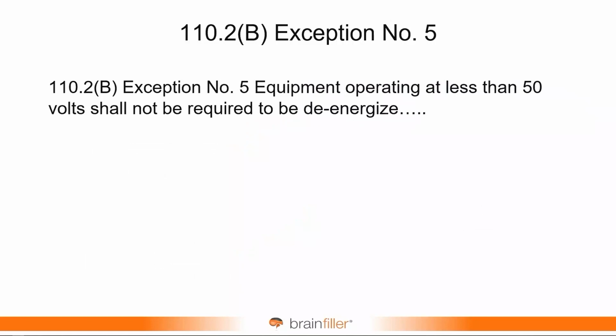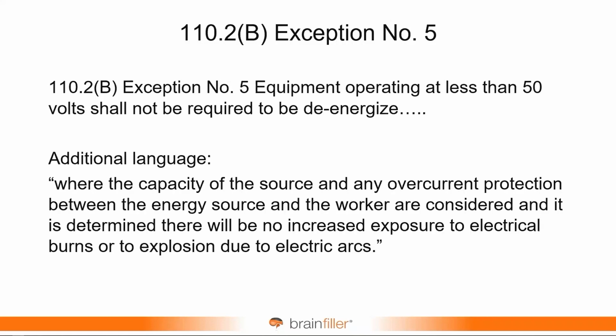There was an additional clarification regarding the 50-volt threshold. For equipment operating at less than 50 volts, there's additional language where the capacity of the source and any overcurrent protection between the energy source and the worker are considered, and it's determined there won't be any increased exposure to electrical burns or to explosions due to arcs. So what this is about: 50 volts has been the threshold. It's in OSHA, it's in NFPA 70E. But the concern is, even though it's below 50 volts, is there enough thermal energy that could cause a burn or some type of a hazard or an injury?